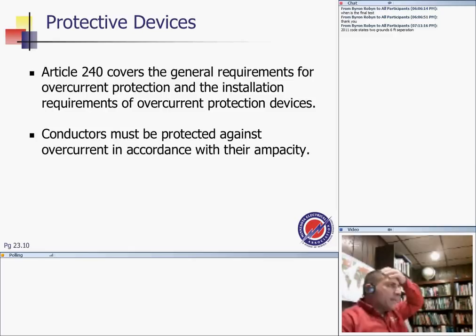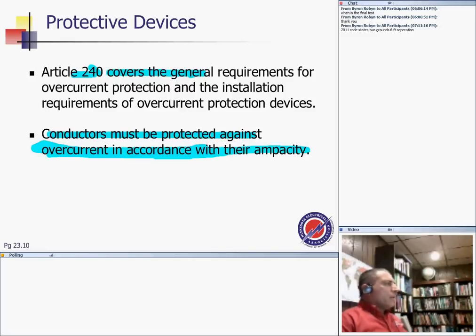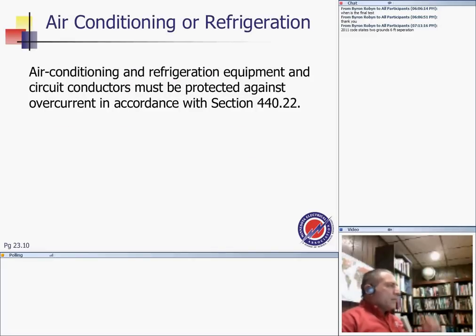Protective devices. Conductors must be protected by an overcurrent protection device. The question is, guys, look at this, it's really interesting. Overcurrent protection device and installation requirement covers. Okay, here, conductors must be protected against overcurrent in accordance with their ampacity. That's a simple rule, but that rule matters all the time. You can't protect a conductor with more than what the conductor can carry.